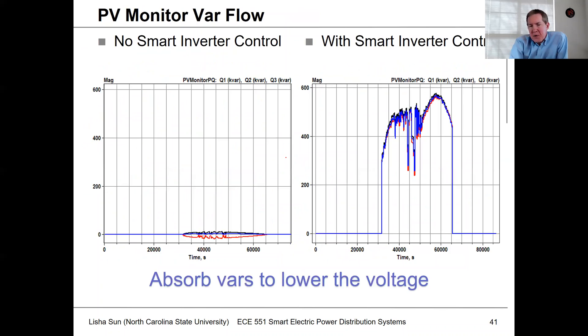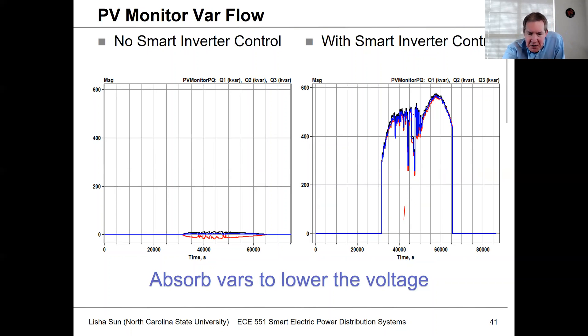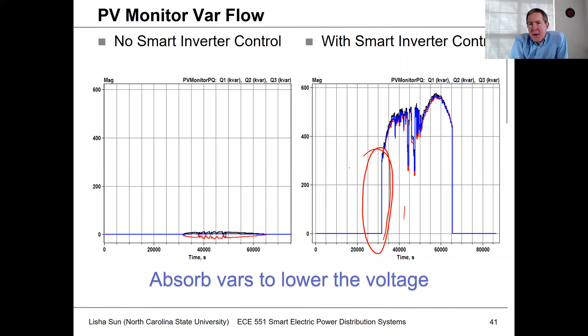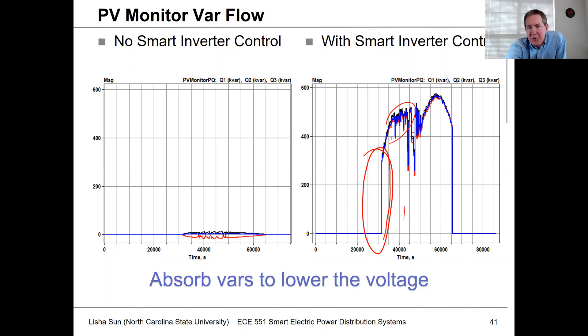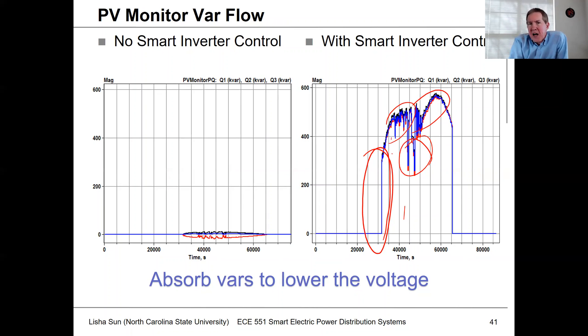When this is implemented in OpenDSS, at the point of interconnection, whenever the voltage gets too high, we sink vars. You can see what's happening over the course of the day: once the PV starts operating, we start sinking vars to pull the voltage back down. As the real power output gets higher, we have to absorb more and more vars, and you can see it adjusting for cloud cover deviations as well.